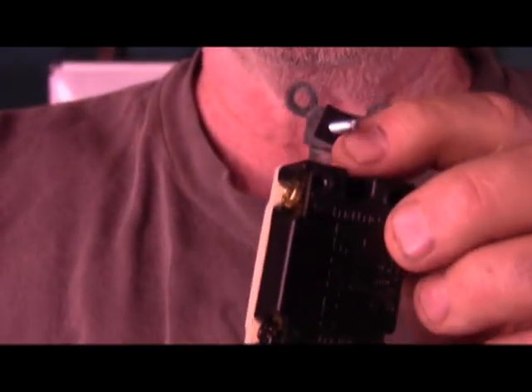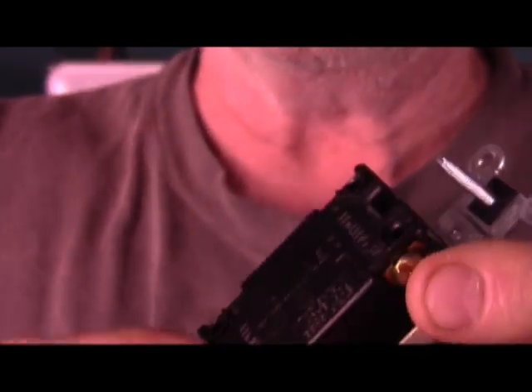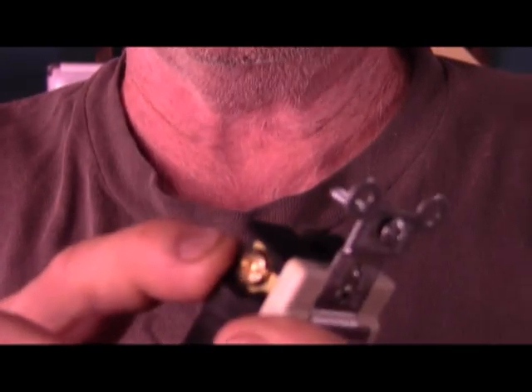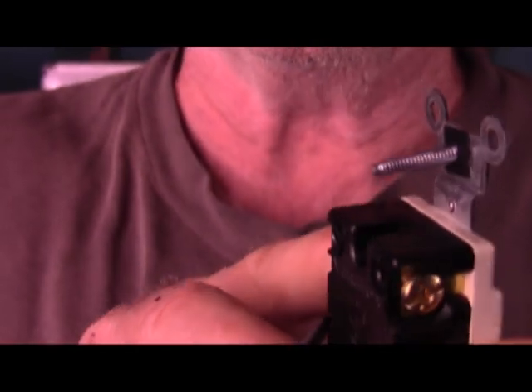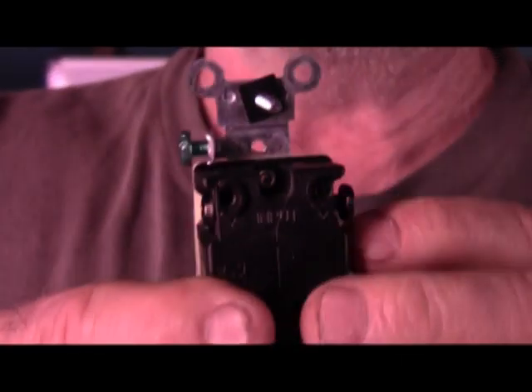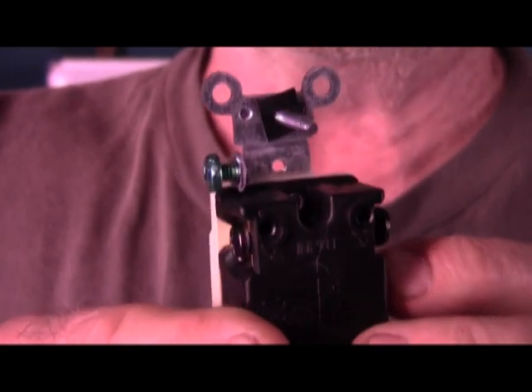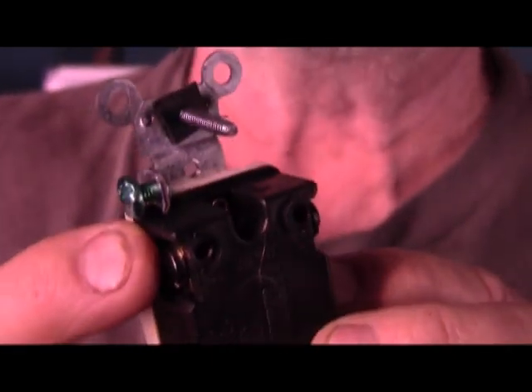Whenever you hook up a four-way, your travelers from one side go to the same color. So a twelve-three coming in from one side will go to the copper-colored screws, and a twelve-three coming from the other side will go to the black-colored screws.